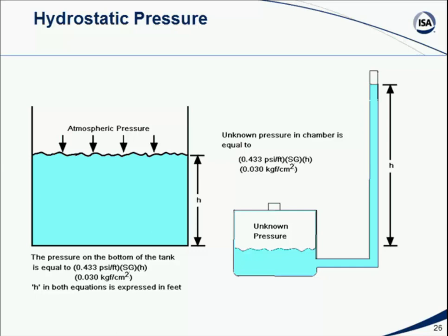We can use this concept to calculate the height of liquid in a tank. Remember, as we said, if we go back to the sight glass example, and we take a tap off the bottom of the tank and bring it to a vertical column of some type, a sight glass for example, the water level in that column is going to be exactly the same as the water level in the tank. So if we can measure the pressure at the bottom of that column, which is in fact the pressure at the bottom of the tank, we can get an idea of how high the fluid level is in the tank. But again, we have to correct.